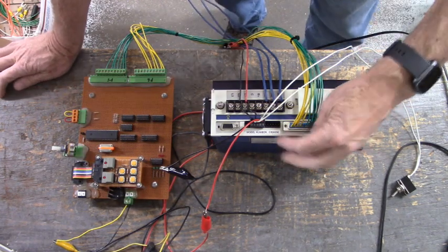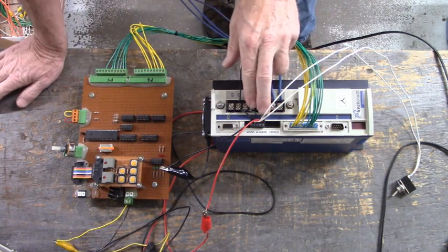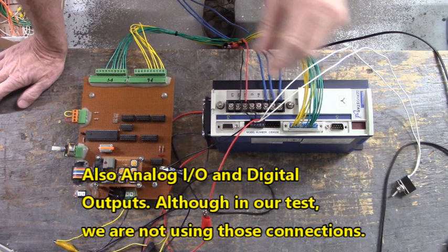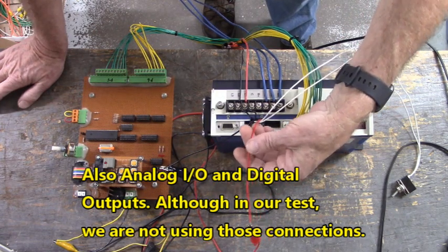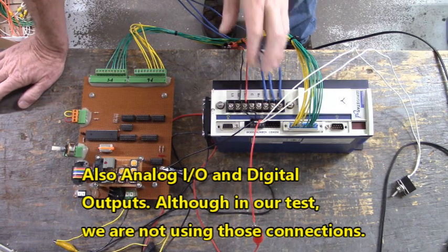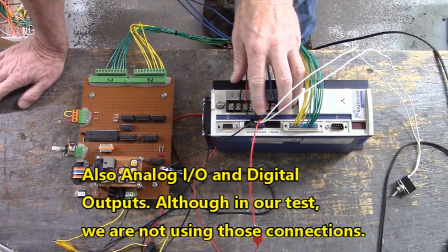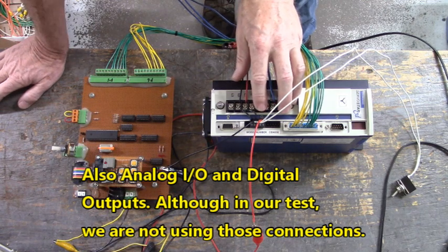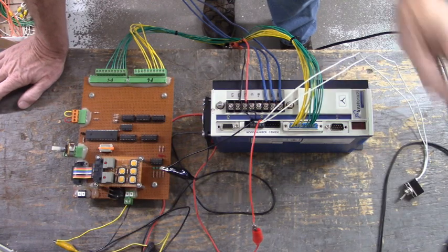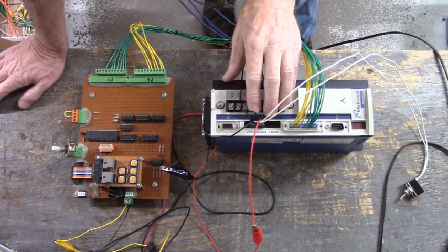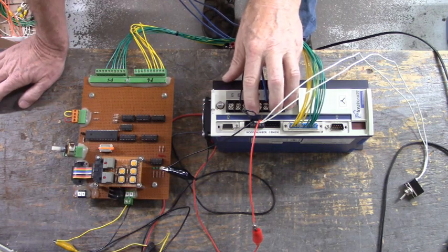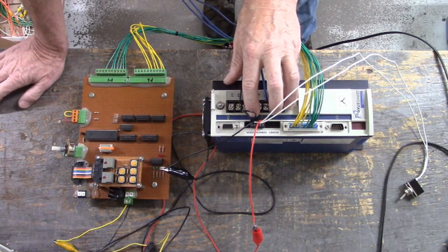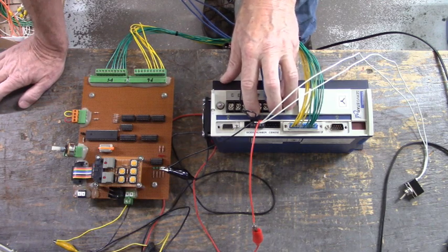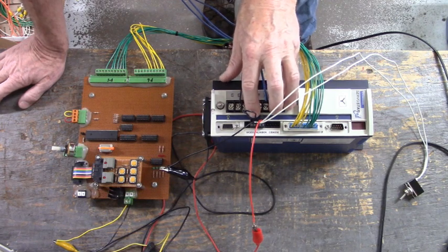Now here on the C3 connector, that's where our enables and our limit switches are connected. I have a 24 volt DC power supply over there. The positive 24 volts DC is going to C3 pin 7. The enable is going to C3 pin 8, which will be switched to the power supply ground. And pins 9 and 10 are the limits. You have a positive limit and a negative limit, or I guess you could call it clockwise limit and counterclockwise limit. So when you ground these inputs back to that 24 volt DC power supply, they're enabled.